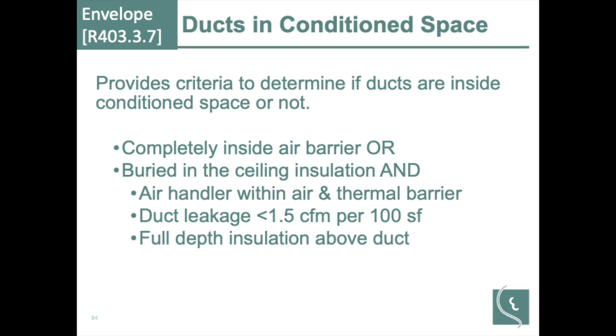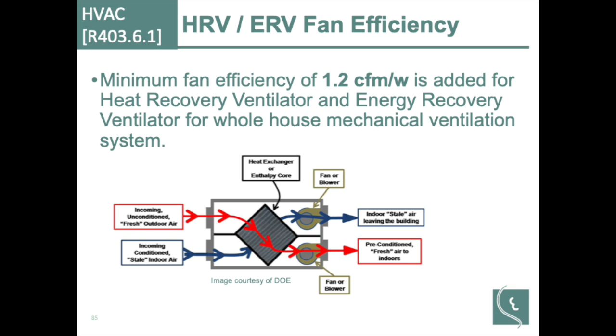So this is the ERV, heat recovery ventilation or energy recovery ventilation. This is just sensible heat right there. This is sensible plus latent. So we're bringing in unconditioned fresh outside air. It goes through a heat exchanger, and this is going to the inside. This is coming from the bathrooms and kitchen. This is the foul air that we're trying to get rid of. Well, this is transferring that heat or coolness in the summer from one airstream to the other, but not mixing them. They're on different sides of a metal plate usually.